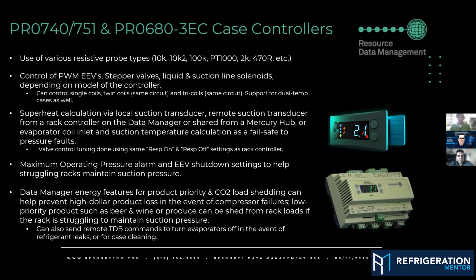Good point. I see a lot of local transducers. That's my preference, because even then you're still going to want to make sure it's reading right for suction. Maximum operating pressure in our case controllers, the case controller doesn't have to talk directly to the rack controller. If it is, then they're sharing the suction pressure.